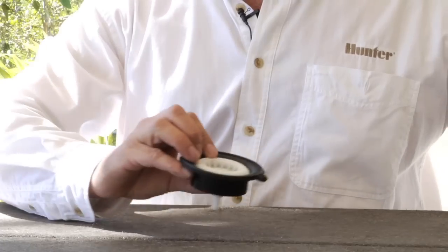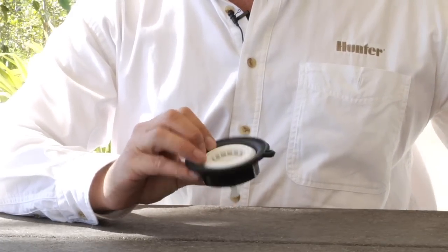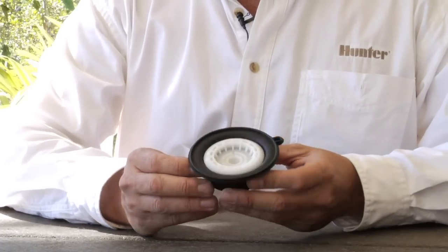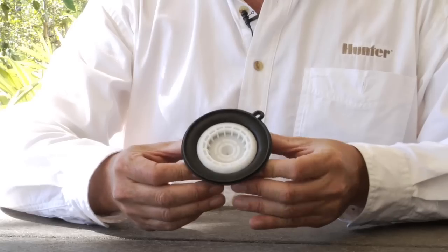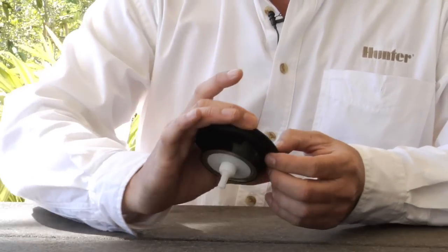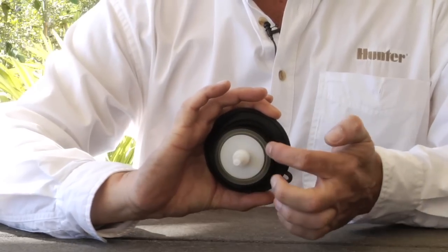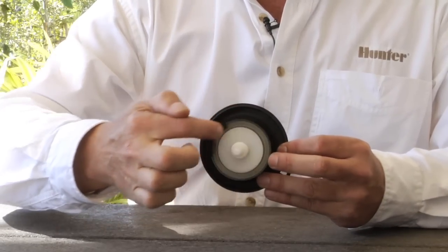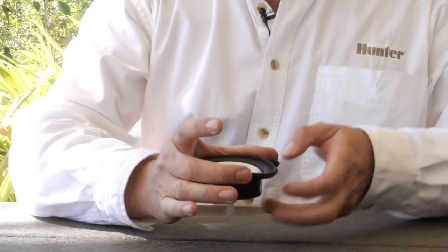The diaphragm operates off of something called surface area differential. And as you can see, the diaphragm sits horizontally in the valve. The top surface of the diaphragm here is much larger diameter than the bottom side. So the difference in surface area is what creates the differential.